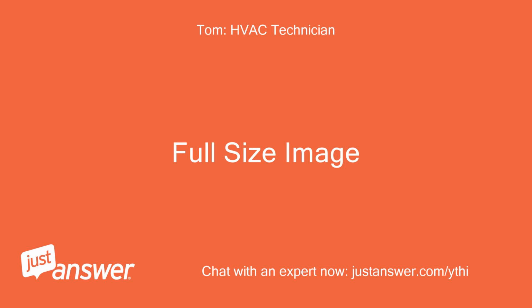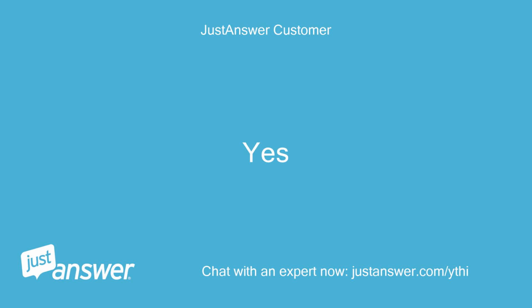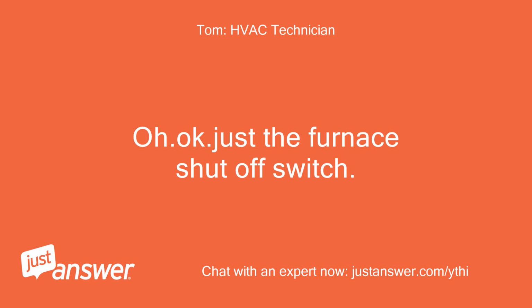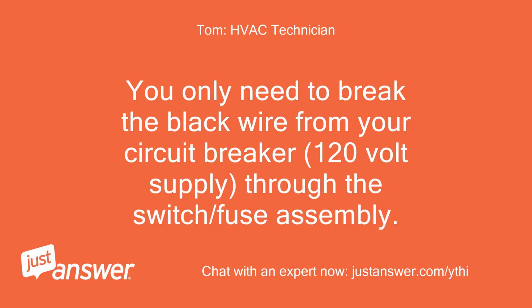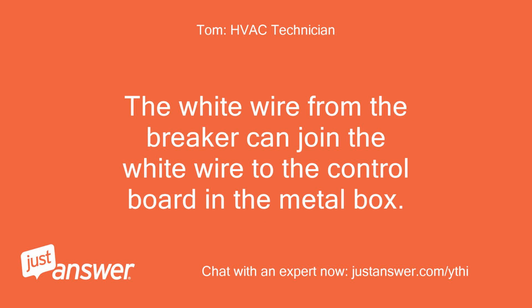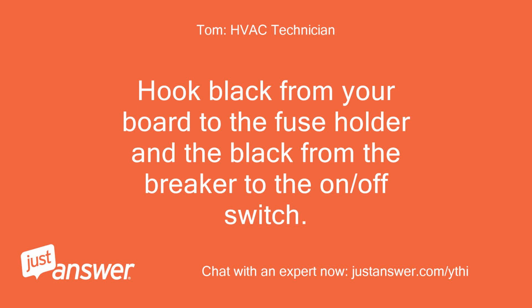Is this it? Yes. Oh, okay. Just the furnace shut-off switch. You only need to break the black wire from your circuit breaker, 120 volt supply, through the switch/fuse assembly. The white wire from the breaker can join the white wire to the control board in the metal box. Hook black from your board to the fuse holder and the black from the breaker to the on/off switch.